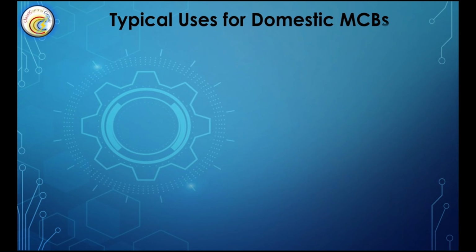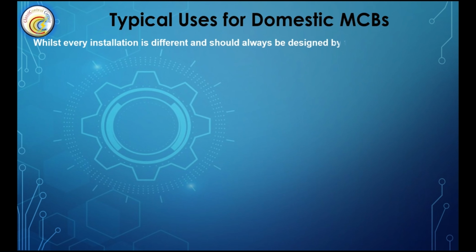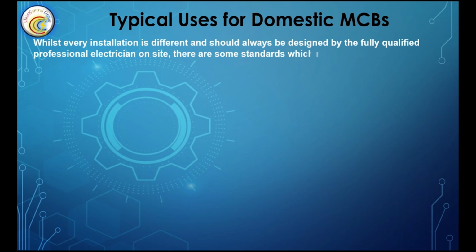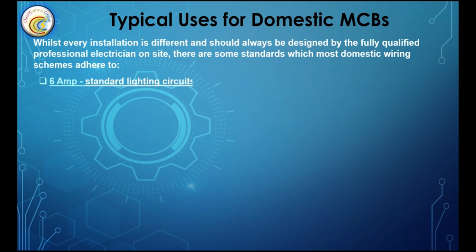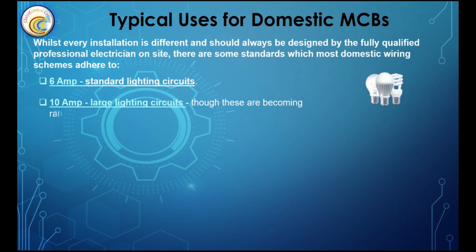Typical uses for domestic MCBs. Whilst every installation is different and should always be designed by the fully qualified professional electrician on site, there are some standards which most domestic wiring schemes adhere to. 6 amp: standard lighting circuits. 10 amp: large lighting circuits, though these are becoming rarer in domestic settings as technology and trends move towards lower energy lighting sources such as LED.